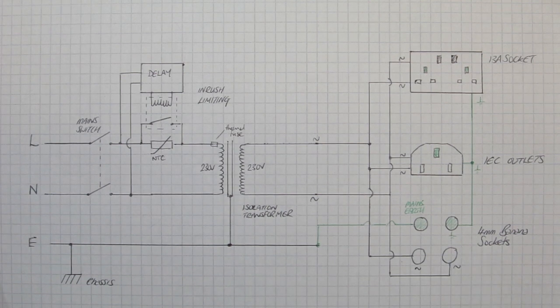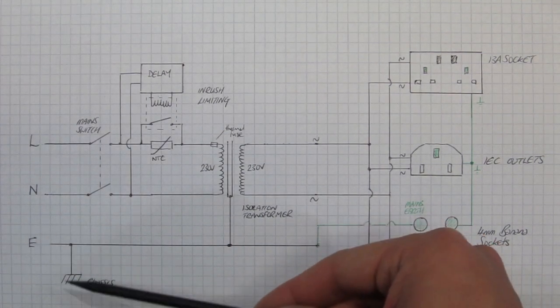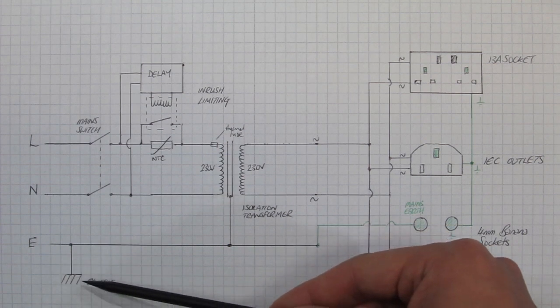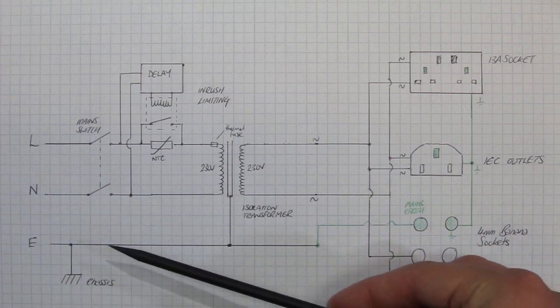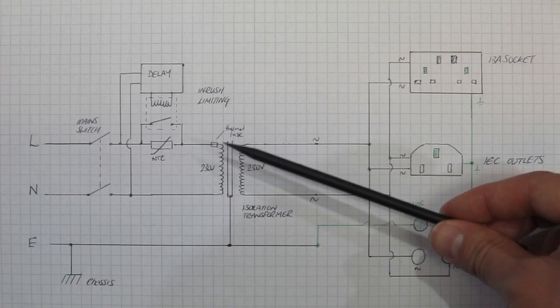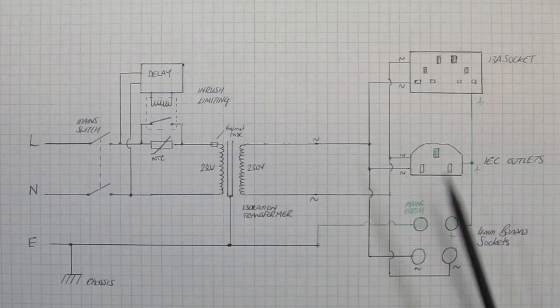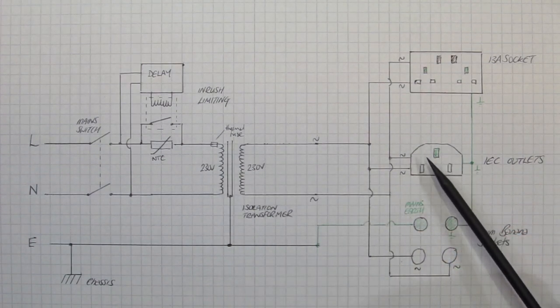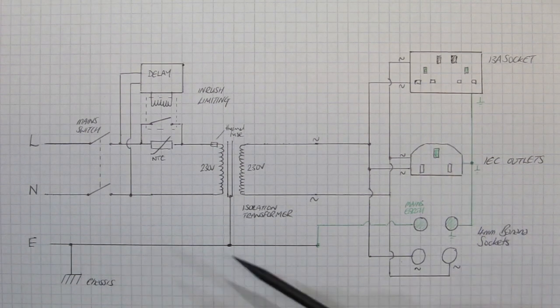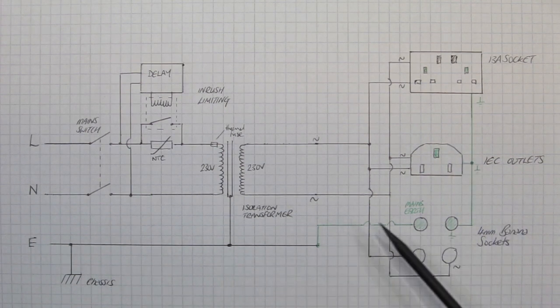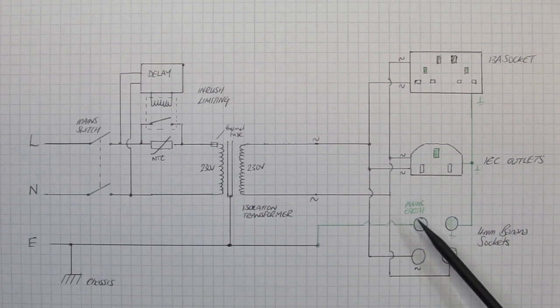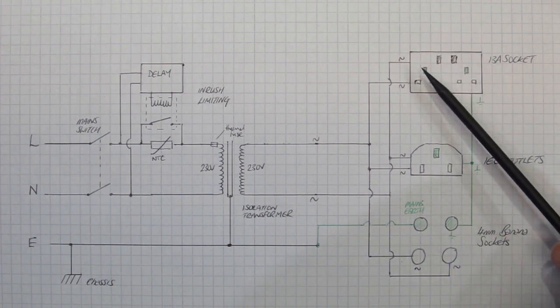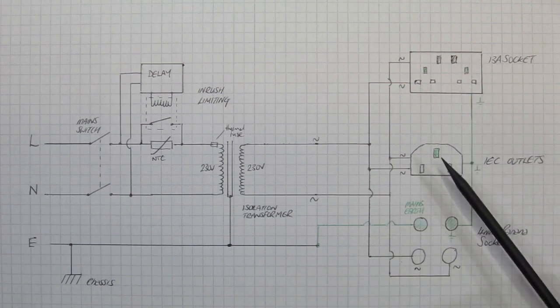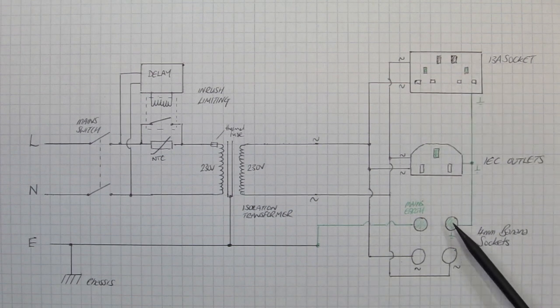So what the unit previously had was the incoming earth connection connected directly to the chassis, connected to the binding post on the front of the unit, to the shield between the primary and the secondary, and then it did previously go directly to the earth pin on the IEC outlets. Instead, what I'd like to do is bring the earth out to the 4mm earth pin on the top of the unit, and then the earth pins from the 13 amp socket and the IEC outlets brought out onto a second earth connection on the top of the unit.